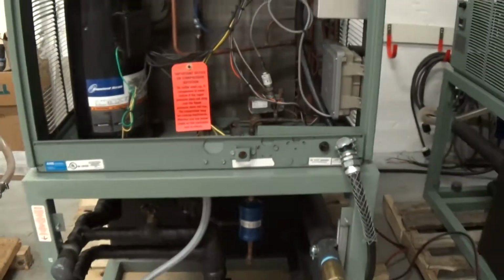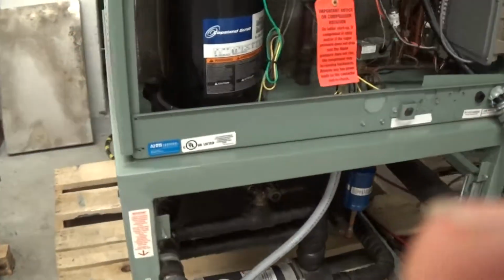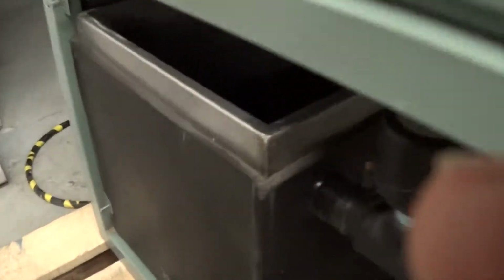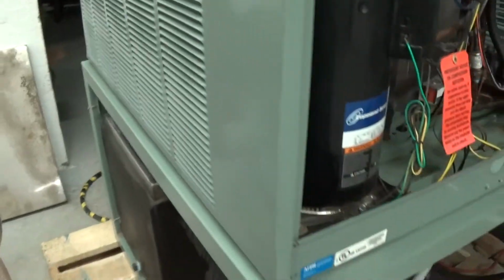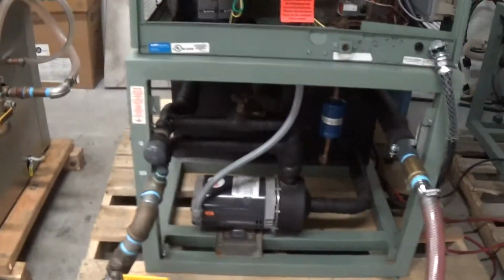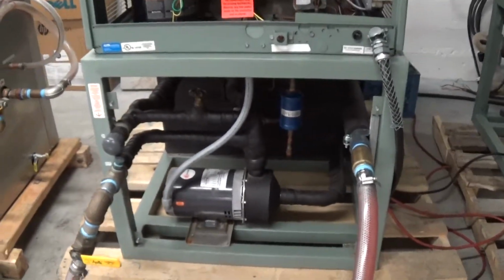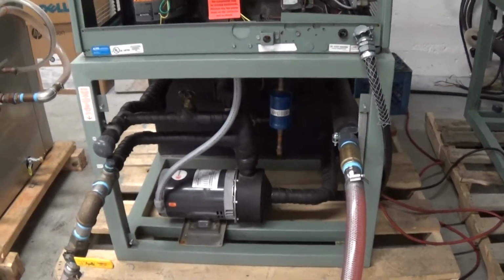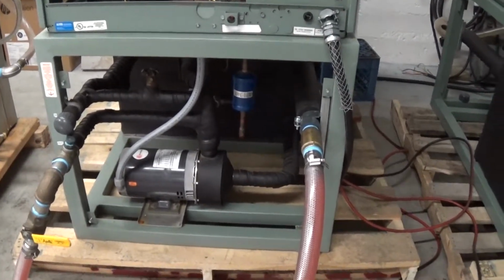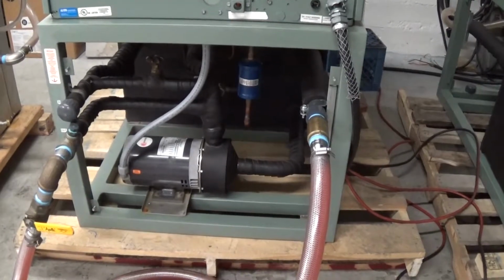Now, with the cold shot chiller, your heat exchanger is actually submerged in the tank down here. Kind of tough to see, but it's there. And what we do for a brewery application is we actually modify the piping of the unit. What Cold Shot calls it is a double return.